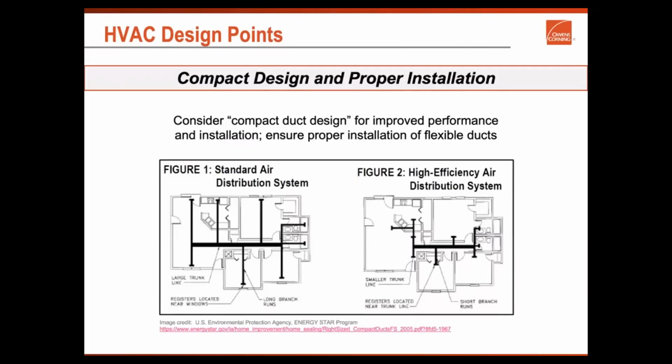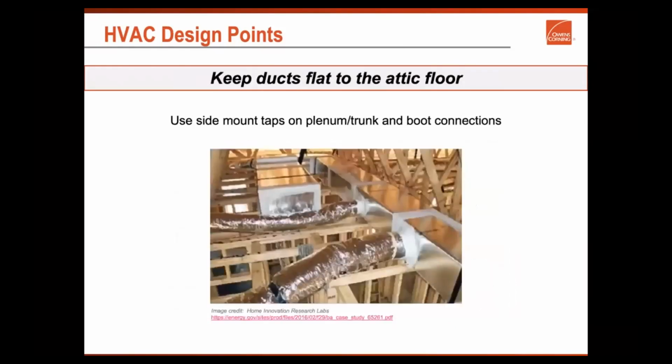If you were doing an energy truss, the duct at the end doesn't matter because it can be continuously buried all the way to the end, right? So that's one of the things we have to consider: we have to pull all these ducts in to make sure that we're going to get proper coverage on the ducts. We use side mount plenum trunks and boot connections to help maintain that. What we don't like is a top mounted one, because that duct has to climb up and then come down, and that affects the airflow and air pressure, especially in a static control system.